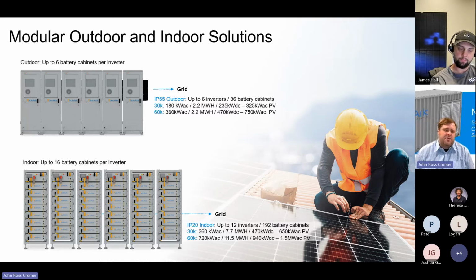At that point, you would likely just put a power distribution block in a junction box, central to each battery stack or group of battery stacks, and wire the batteries into a power distribution block to aggregate it before landing on the inverter. So with 16 battery cabinets per inverter, you would have 2 power distribution blocks, 8 battery cabinets per power distribution block, then going into the inverter.